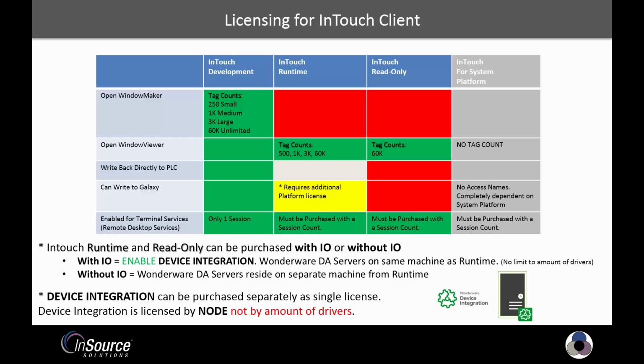However, there are different tag counts for runtime: 500 tag, 1000, 3000, and then jumping all the way to 60,000. The third type is called read-only. Read-only functions just like a runtime license, but it does not allow an operator to write back to the PLC, nor can he or she acknowledge an alarm. The last type is called InTouch for System Platform. This is when you're using InTouch in conjunction with the System Platform Galaxy. Here, there are no tag counts that we deal with.